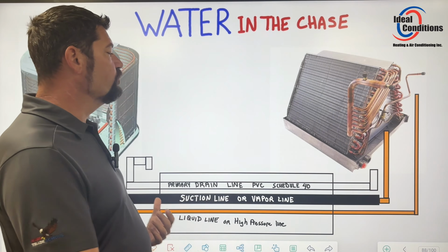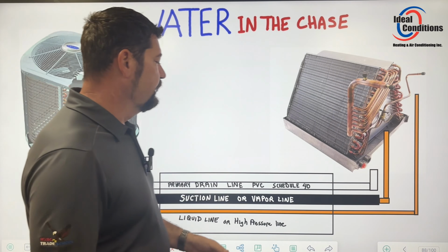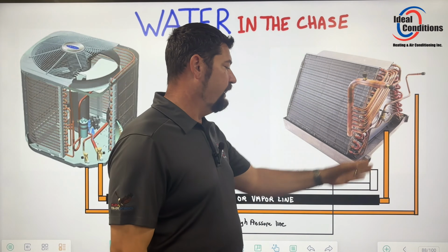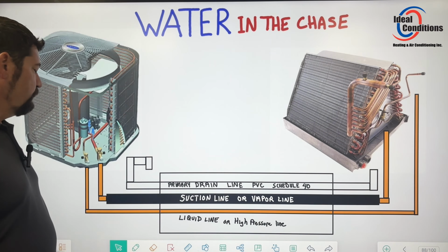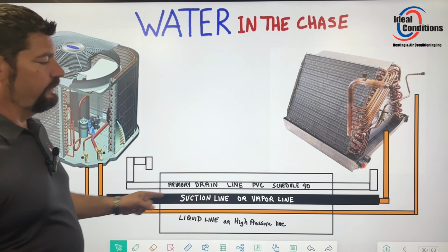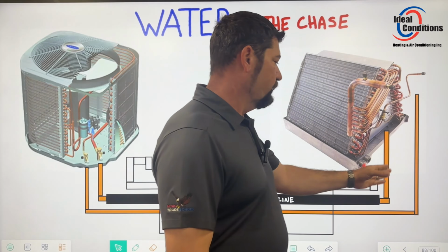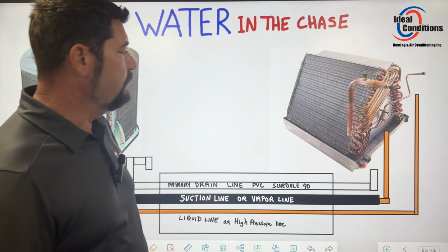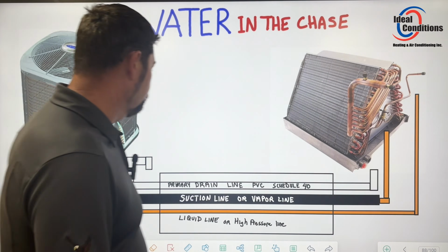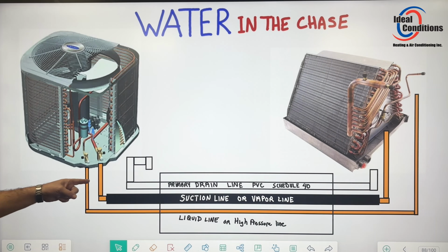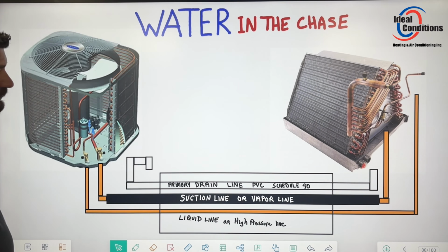They're always going to change, cold or hot, and you don't want that to add or take away from those values. So I would use 1/2 inch Armaflex on your copper suction line. That way you're getting that accuracy of whatever you measure here, it being the same within a degree or so of what you're measuring here at the service valve.